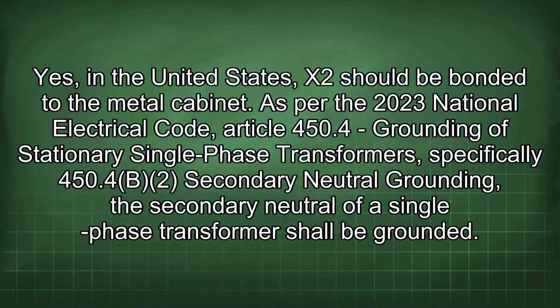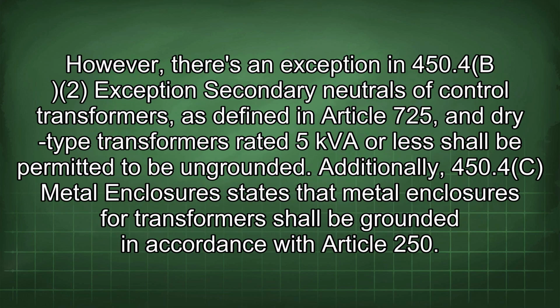Yes, in the United States, X2 should be bonded to the metal cabinet. As per the 2023 National Electrical Code, Article 450.4, grounding of stationary single-phase transformers, specifically 450.4(B)(2) secondary neutral grounding, the secondary neutral of a single-phase transformer shall be grounded. However, there's an exception in 450.4(B)(2): secondary neutrals of control transformers, as defined in Article 725, and dry-type transformers rated 5 kVA or less shall be permitted to be ungrounded.